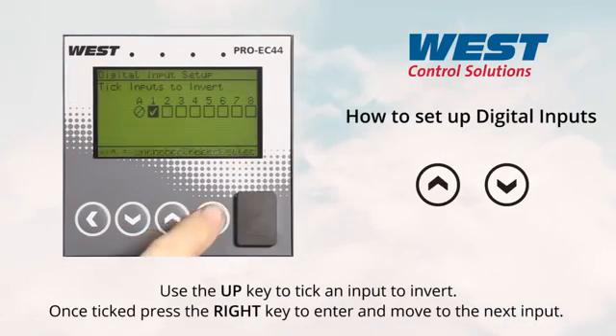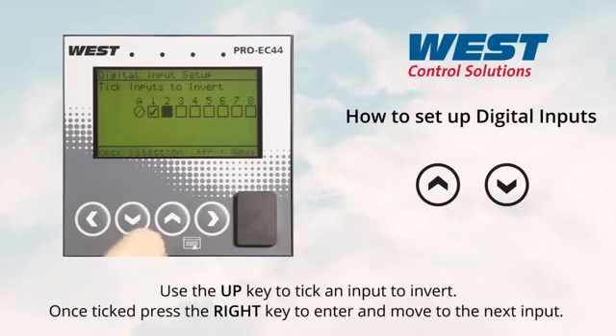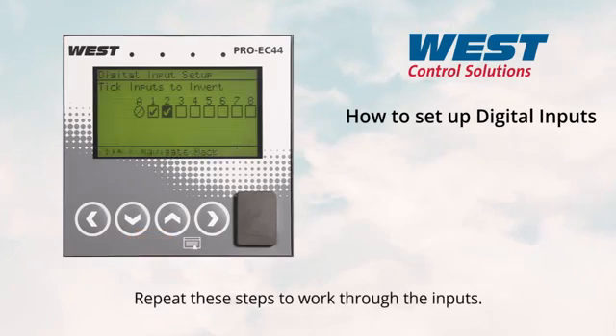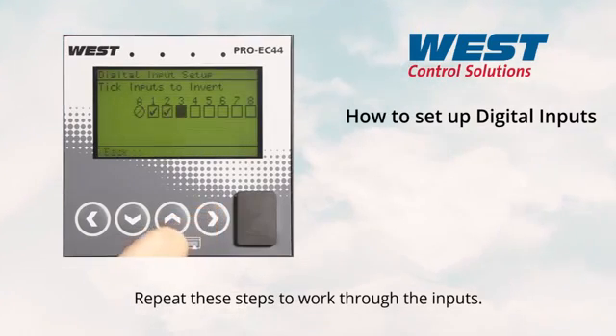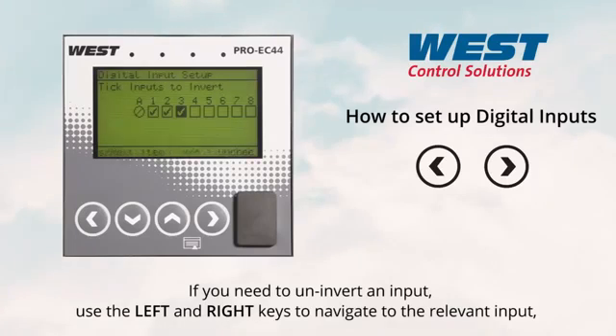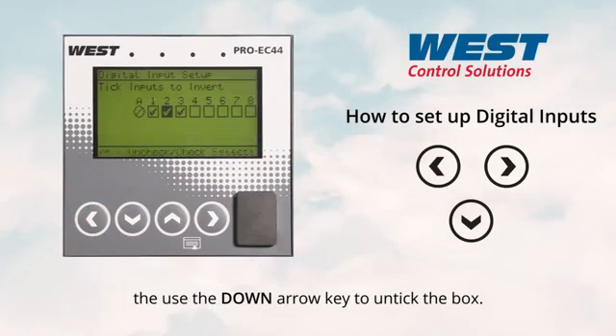Use the up key to tick an input to invert. Once ticked, press the right key to enter and move to the next input. Repeat these steps to work through the inputs. If you need to un-invert an input, use the left and right keys to navigate to the relevant input, then use the down arrow to untick the box.